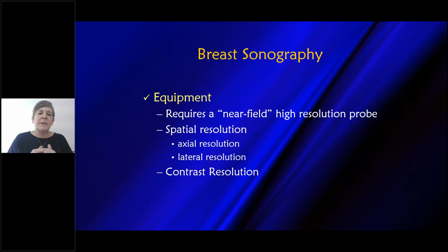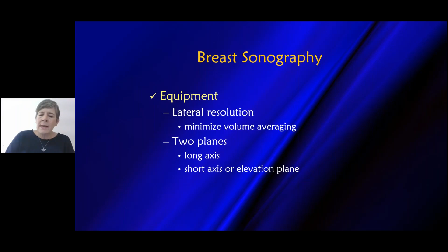So proper equipment, once again, requires excellent near field resolution, good spatial resolution, which is your axial and lateral, and also good contrast resolution. Lateral resolution is what helps minimize your volume averaging. If we look at a transducer, there are 2 planes we deal with: the long axis, and then the short axis or elevation plane focus. On the long axis, we can control your focal zones. Moving those up and down will help give you better image quality. The elevation plane is where we don't have any control.